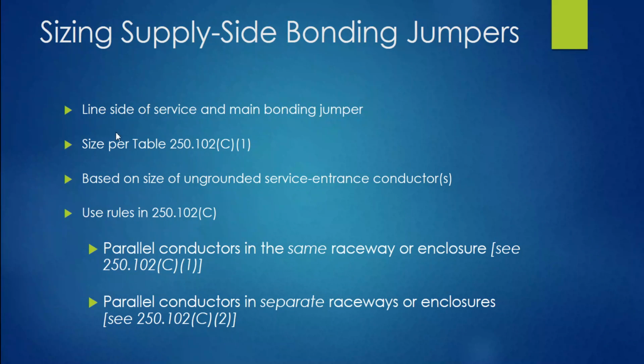Now let's talk about sizing. On the line side of the service and main bonding jumper, okay, so we're on the line side of the service and main bonding jumper. We've already sized the main bonding jumper. We get that. Now, size per Table 250.102(C)(1). So that gives us our rules, and it says based on the size of the ungrounded service entrance conductors, use the rules in 250.102(C). Now, if it's parallel conductors run in a single raceway, just one raceway, then we're simply going to go to the table, and it's very easy to select it at that point under 250.102(C)(1).